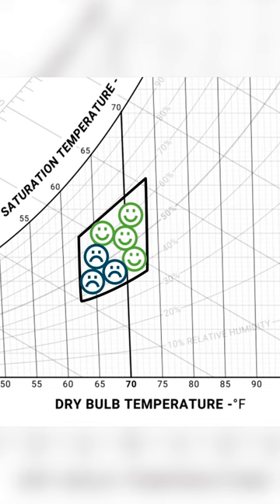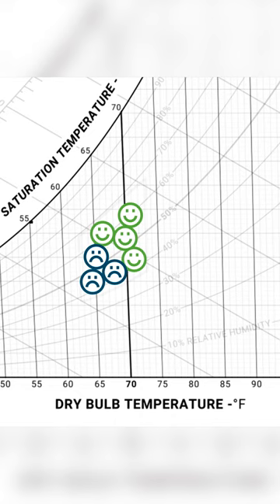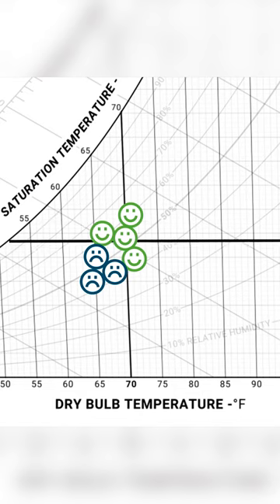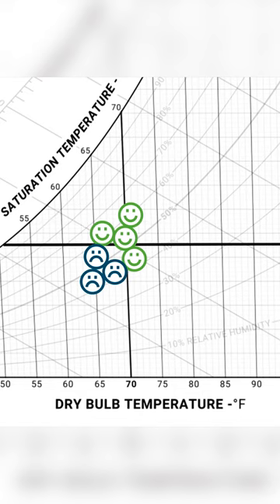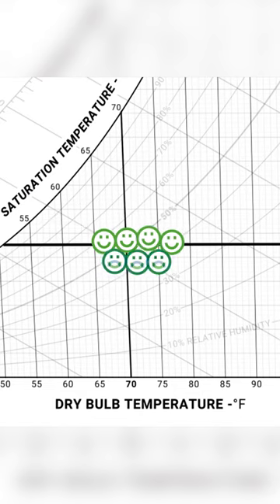The best thing we found was actually dropping the dew point lower than what you'd typically be trying to shoot for on a space. So normal occupied space, people are often trying to shoot for around a 55 dew point. We started to find it's more like the 51, 52 degree dew point, sometimes even a little bit lower.